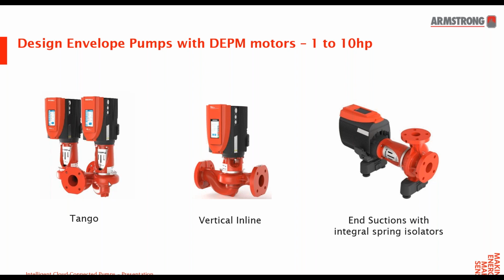It's worked very well. The key is to understand that the limitation is that it's for single zone applications, and not try to apply it to other multi-zone applications. Single zone applications are more than fine for sensorless control, and we would say 90% of the market is single zone applications. Great, thank you.